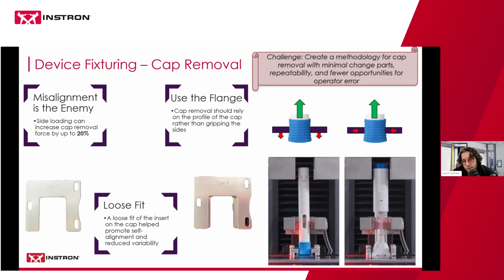And then the final question was, all right, so we know this is the design. Should we make a tight fit or a loose fit for how we interface with that cap? We had different customers request different things, but we did a lot of testing and found that a loose fit that is not over constraining the cap resulted in better, more repeatable data. Primarily because by leaving that loose, you actually allow for some self alignment as you pull the cap off, which again helped reduce that variability.